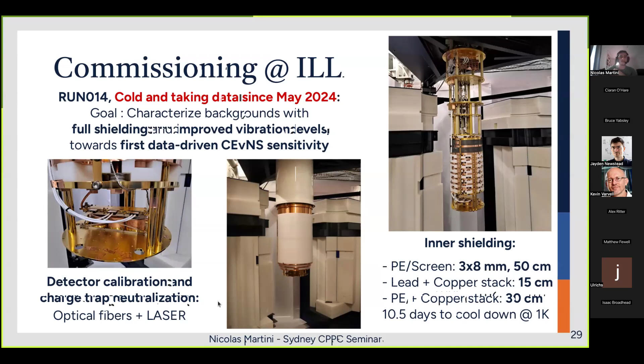And in terms of charge trap neutralization, well, we are operating our crystals at a certain bias, and after quite some time and a certain number of events in our detectors, it creates some charge traps which degrade our ionization collection. And one thing you might want to do to improve your ionization performances is to shake all of these charge traps to get them in a better state. And you can do that also with the laser by just bombarding your crystal with a huge number of photons for a short period of time to get everything to be in its original place.